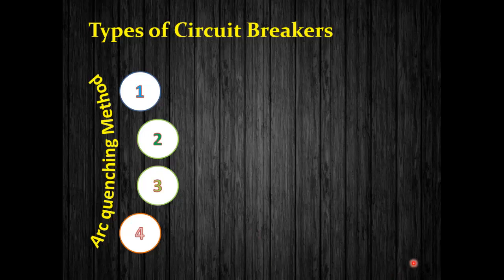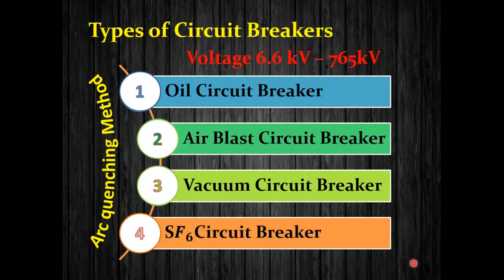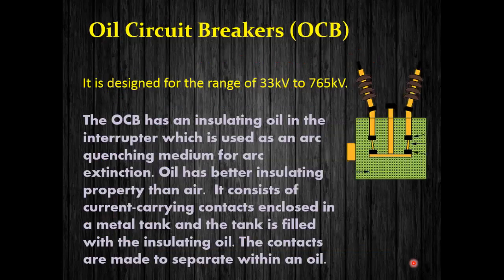Welcome to this video where we will learn about different types of circuit breakers for high voltage — voltage ranging between 6.6 kilovolts to 765 kilovolts. The main purpose of a circuit breaker is to open or break the circuit during a fault condition, and in that condition its purpose is to properly quench the arc produced during contact opening. Based on the arc quenching method, we have four different types: oil circuit breaker, air blast circuit breaker, vacuum circuit breaker, and SF6 circuit breaker.